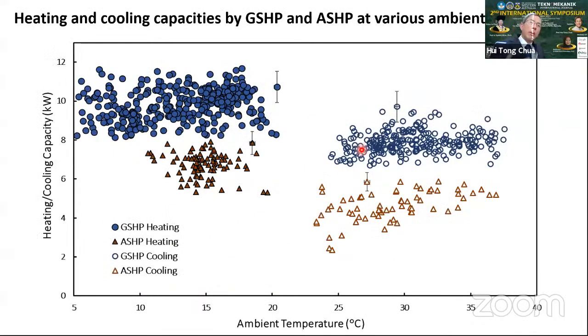So I want to now come to the heating and cooling capacities. Obviously, because of human research ethics oversight, we have no control whatsoever over the behavior of the occupants of the two properties, and we really shouldn't exert any control. But they quite gratifyingly self-assemble toward a fairly consistent indoor condition. In terms of the absolute heating and cooling capacities of the two properties, certainly the ground source heat pump is consuming a greater capacity, for both heating and cooling, compared with the corresponding air source heat pump capacities.